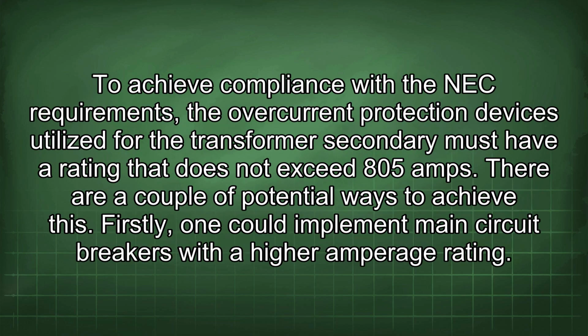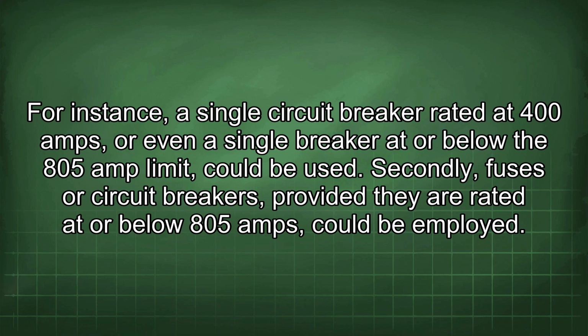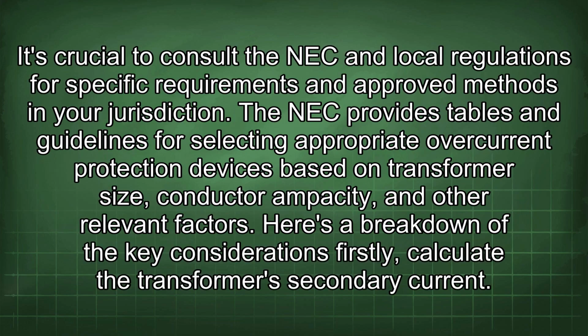To achieve compliance with the NEC requirements, the overcurrent protection devices utilized for the transformer secondary must have a rating that does not exceed 805 amps. There are a couple of potential ways to achieve this. Firstly, one could implement main circuit breakers with a higher amperage rating. For instance, a single circuit breaker rated at 400 amps, or even a single breaker at or below the 805 amp limit could be used. Secondly, fuses or circuit breakers, provided they are rated at or below 805 amps, could be employed. It's crucial to consult the NEC and local regulations for specific requirements and approved methods in your jurisdiction.